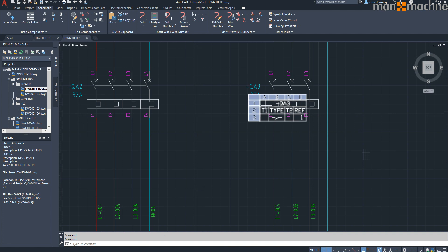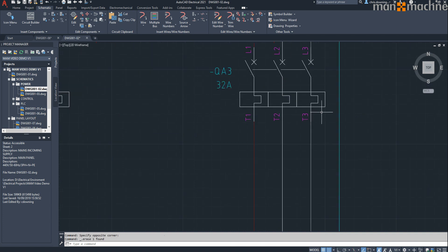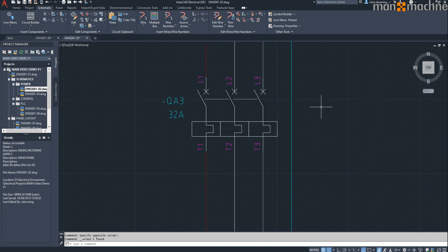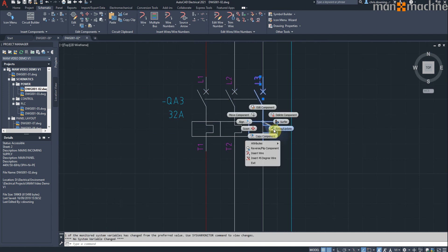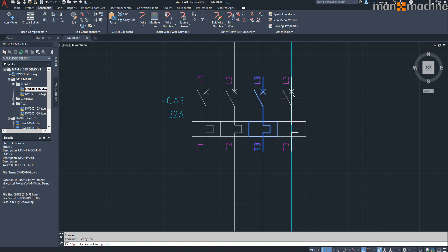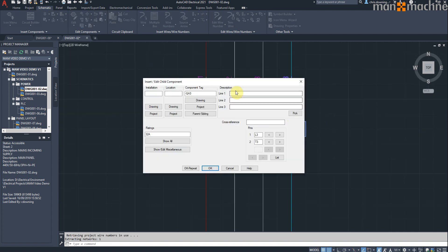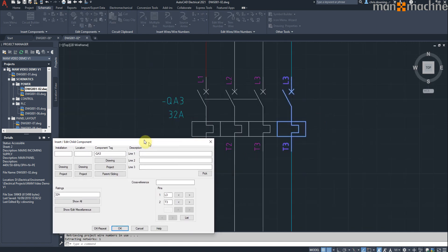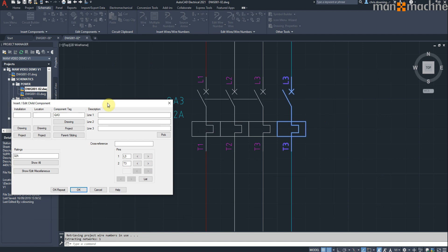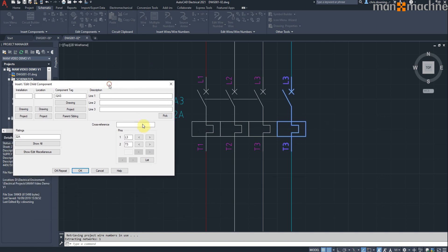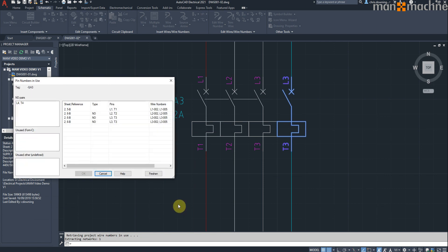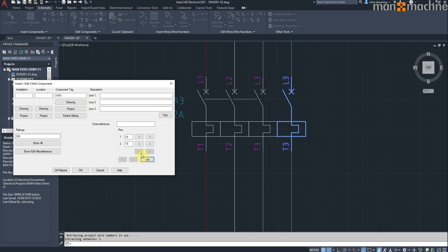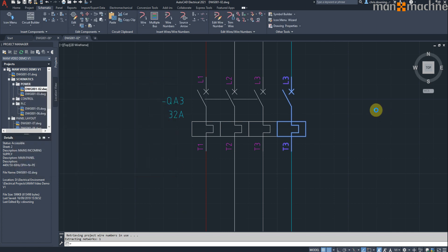You can see it's syncing it up there with my panel layout. Let's get rid of this reference. We don't need the reference in this case. So you can see there's my parent symbol and my two child symbols linked to the parent. And just to finish the symbol off, I'll click in there and copy the third pole to make a fourth. You can see, because it's a copy of the third, the pins there are picking up the same as the third pole. But if I click list, you can see I've got a spare pole there, not used, L4 and T4, and I can select those and put them in like so.